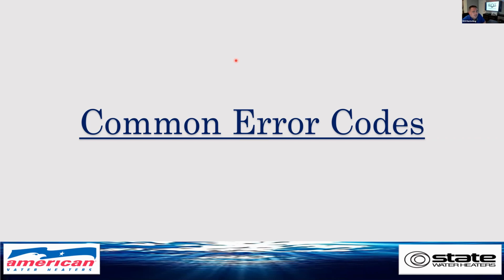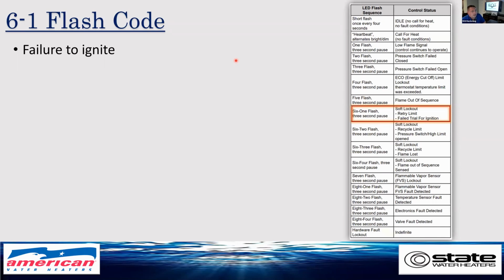Common error codes. There's 16 different error codes in total. We're going to cover 3 error codes that cover about 80% of the codes found out in the field. So a 6-1 flash code, failure to ignite. First, check to see if you have flame. If you did not get flame, first thing to check would be your incoming gas pressure to make sure somebody didn't shut off a valve. Is it an LP install where their tank has gone empty? Because 20% of a propane tank is considered empty.